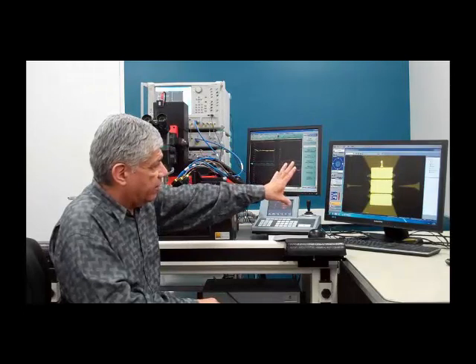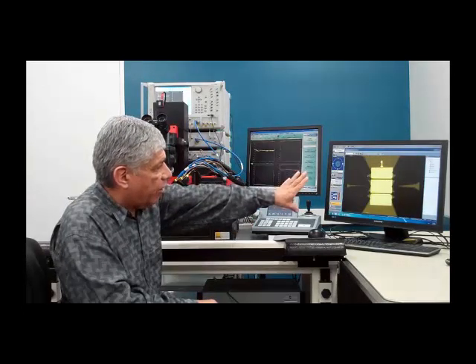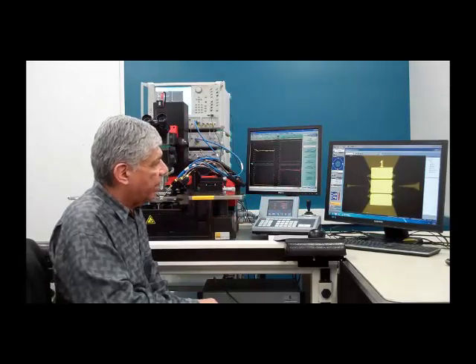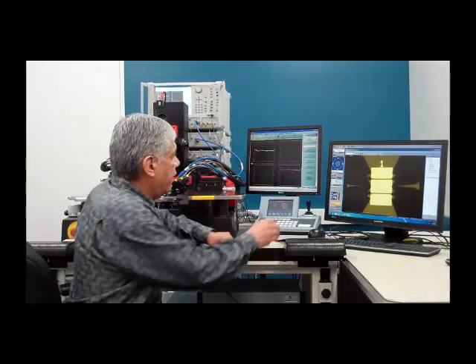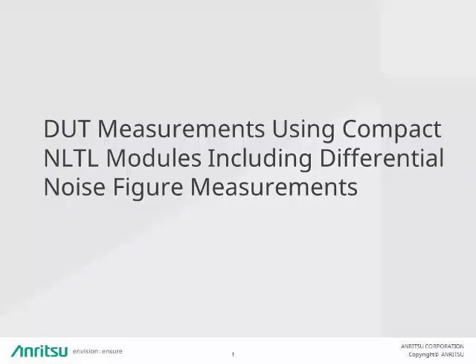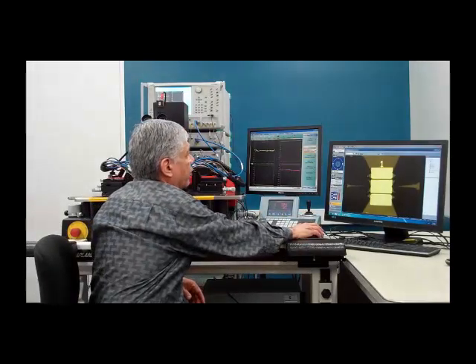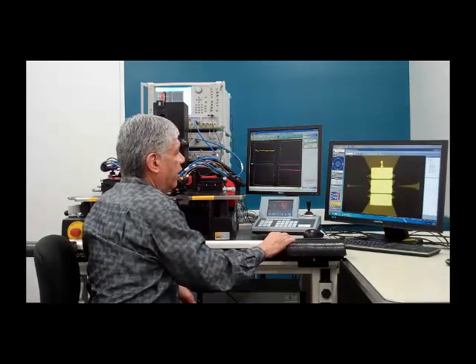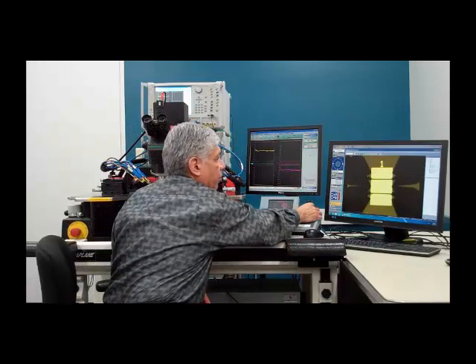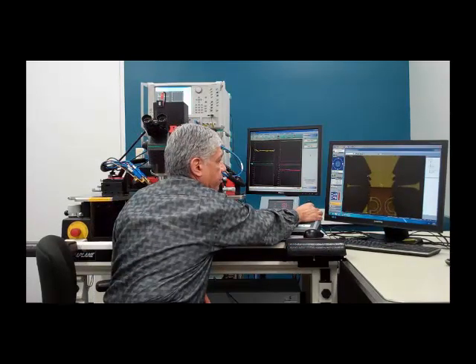So now that I've got things aligned with these probes and this cal substrate, I can then move on to my devices itself. And so again, you can see here that I've got a number of devices to go through, and I'll first select the reflected device and then start making my measurements. So now we're ready to start making measurements of our calibration standards. So I'll first go to the reflection devices and set up for my short. And so now we can go and call up our shorts and land on them in order to make our calibration of our reflection devices.